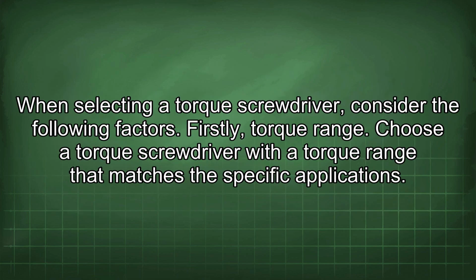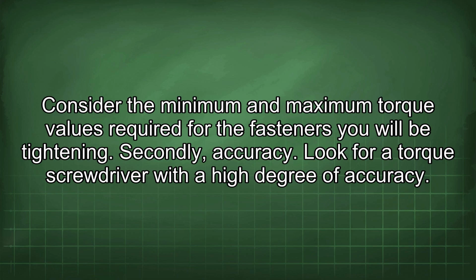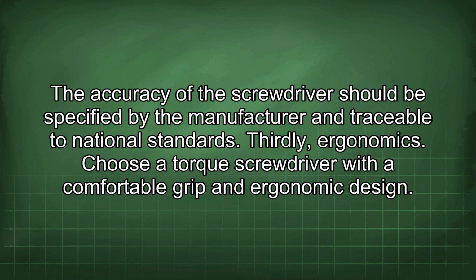When selecting a torque screwdriver, consider the following factors. Firstly, torque range. Choose a torque screwdriver with a torque range that matches the specific applications. Consider the minimum and maximum torque values required for the fasteners you will be tightening. Secondly, accuracy. Look for a torque screwdriver with a high degree of accuracy. The accuracy of the screwdriver should be specified by the manufacturer and traceable to national standards.